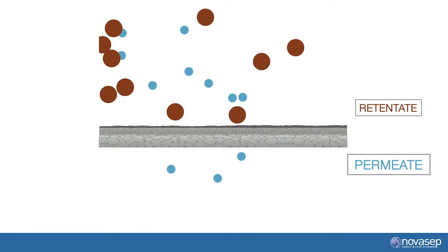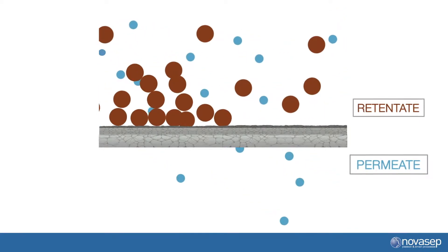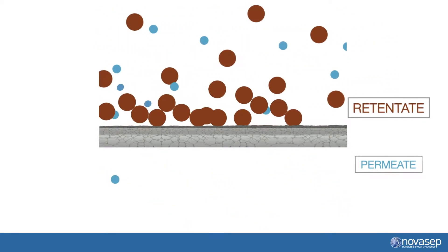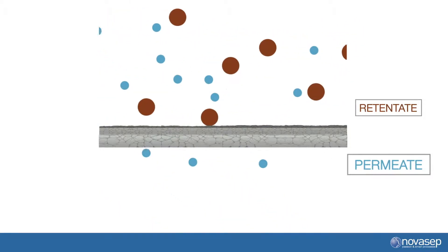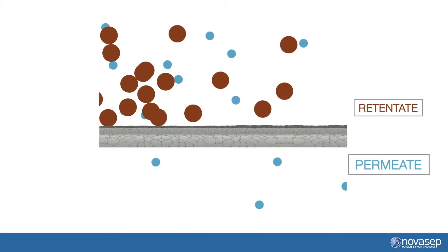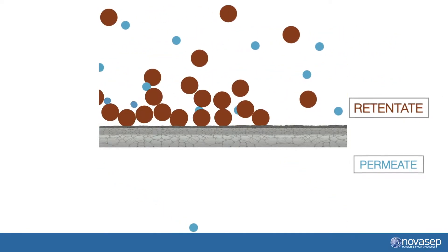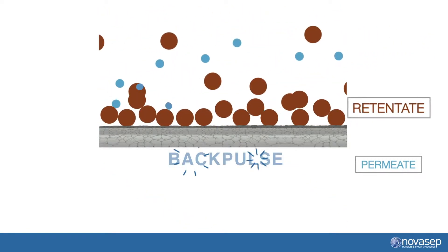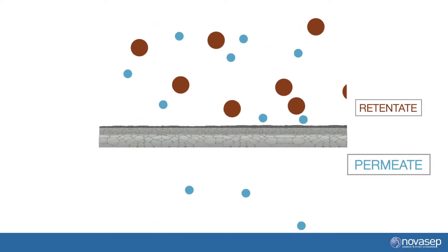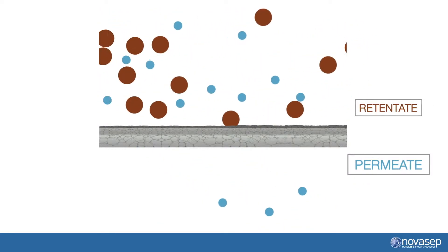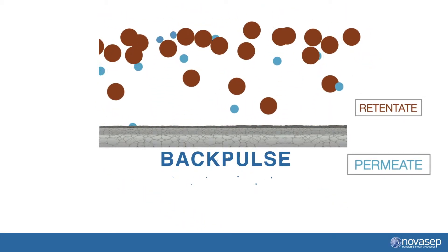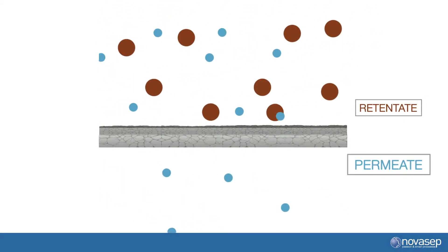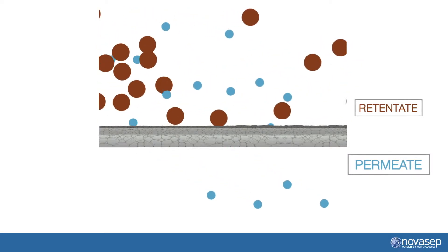In production, transmembrane pressure or TMP is a driving force that allows the permeate to pass through the membrane despite the natural resistance to do so. Resistance to permeate flow is a combination of the inherent resistance of the membrane and the additional resistance caused by the fouling layer. When this additional resistance is too high, permeate flux decreases.